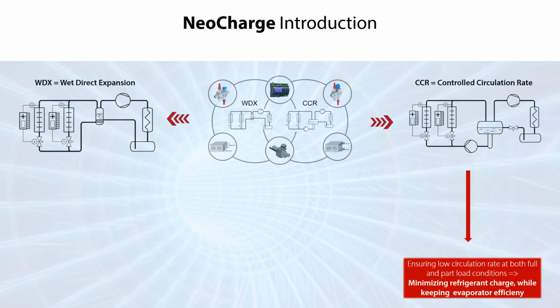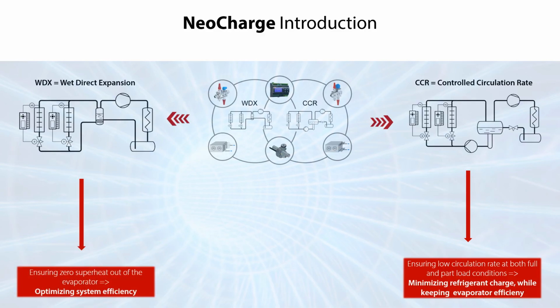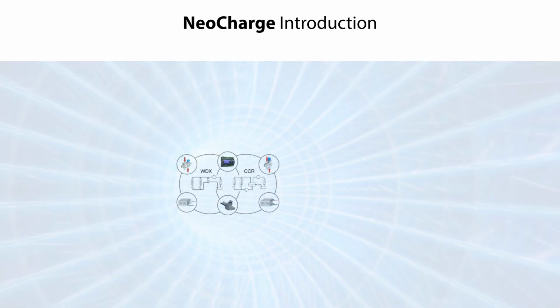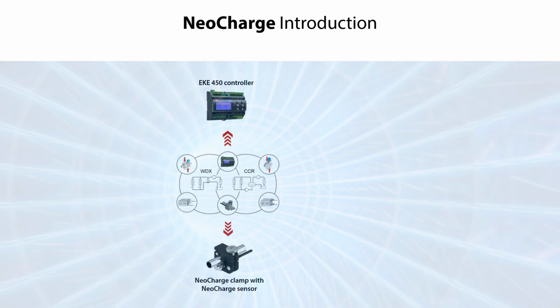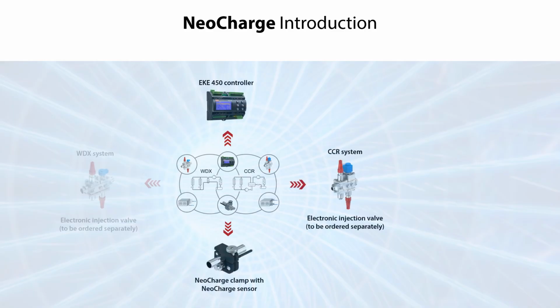The other application is wet direct expansion systems, also called WDX systems, which are traditional direct expansion systems. Here the Neocharge ensures zero superheat out of the evaporator, thereby optimizing the system efficiency. The Danfoss Neocharge consists of an EKE 450 controller, a Neocharge sensor and a clamp to fix the sensor to the evaporator tube, electronic injection valves, which are specifically designed for CCR and WDX systems, and which should be ordered separately, and finally, a solid-state relay.